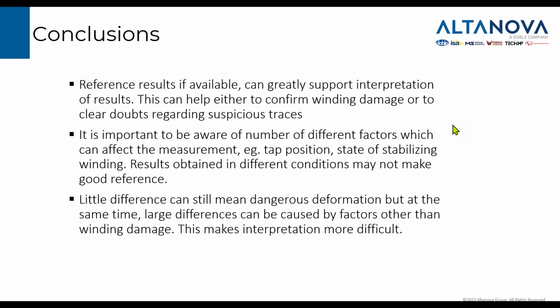If you cannot get a good comparison with reference results, try to identify the difference. Maybe this is one of the influencing factors, and just by changing something in your test, you can match the reference results and tell, okay, the transformer is in good condition. Otherwise, you will have to tell something about this measurement, and it's not going to be that easy. It is also important to be aware of a number of different factors which can affect the measurement, like tap position, state of stabilizing winding. So results obtained in different conditions may not make a good reference. This is what I just said in the first conclusion.